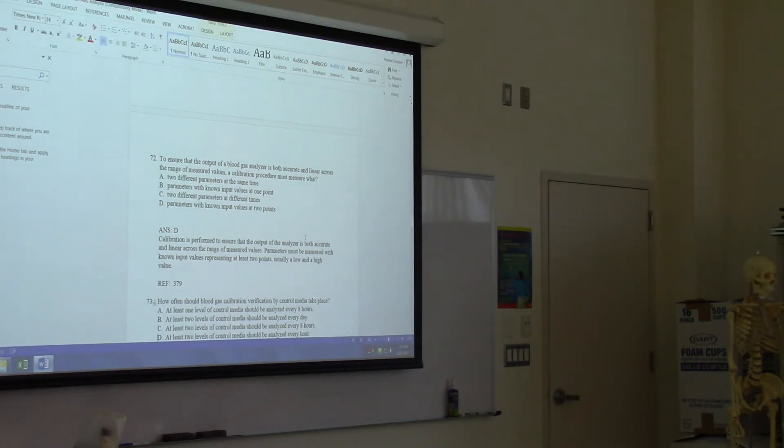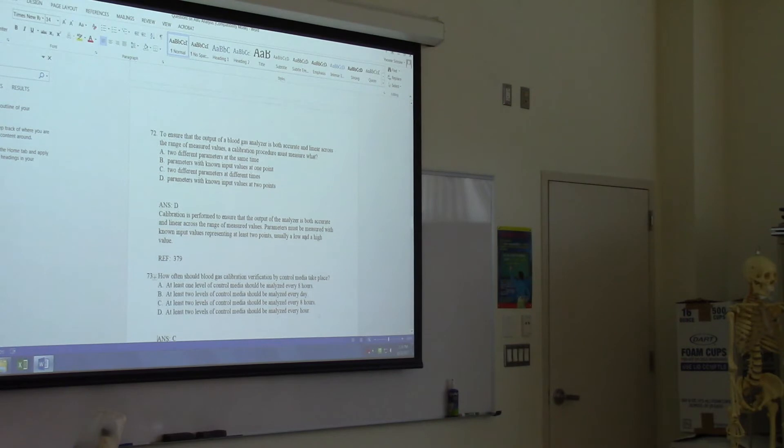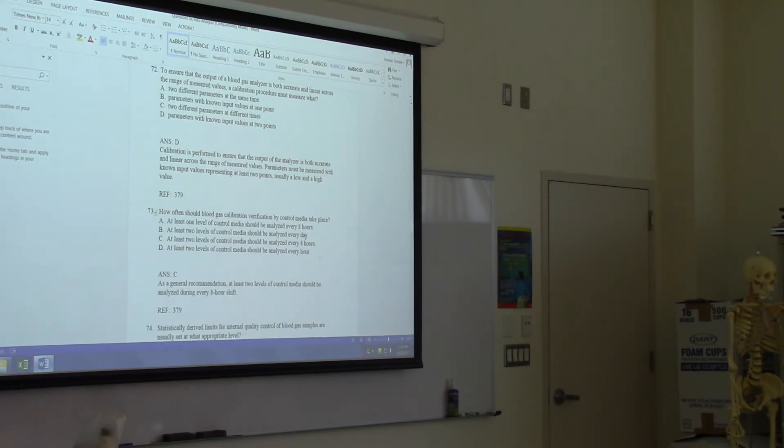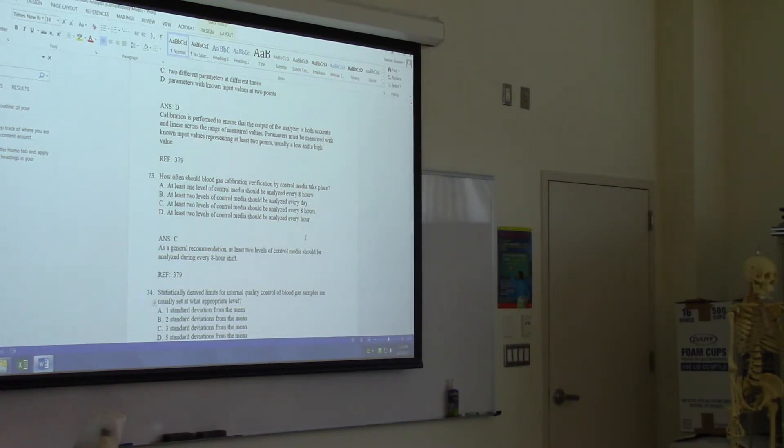How often should blood gas calibration verification by control media take place? Yeah, two levels every eight hours. Statistically derived limits for internal quality control of blood gas samples are usually set at what appropriate level? Two standard deviations.